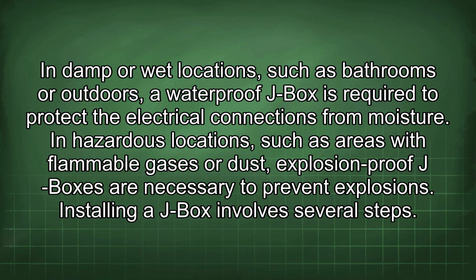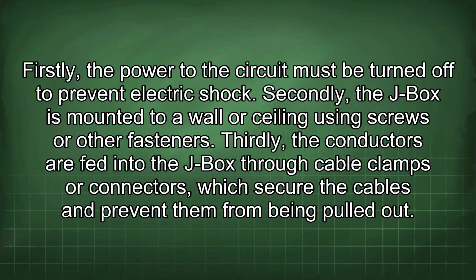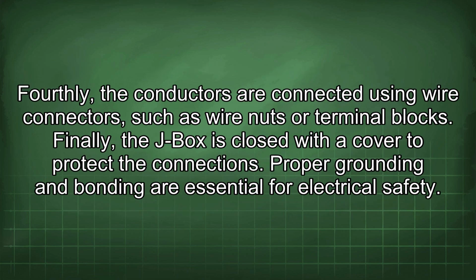Installing a J-box involves several steps. Firstly, the power to the circuit must be turned off to prevent electric shock. Secondly, the J-box is mounted to a wall or ceiling using screws or other fasteners. Thirdly, the conductors are fed into the J-box through cable clamps or connectors, which secure the cables and prevent them from being pulled out. Fourthly, the conductors are connected using wire connectors such as wire nuts or terminal blocks. Finally, the J-box is closed with a cover to protect the connections.